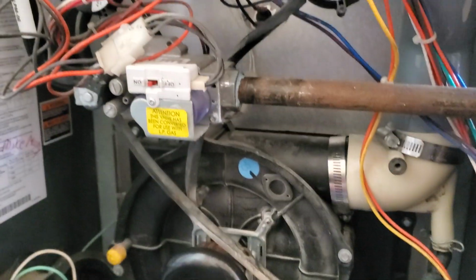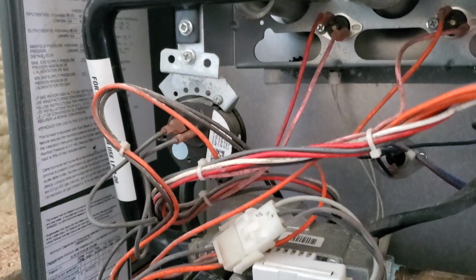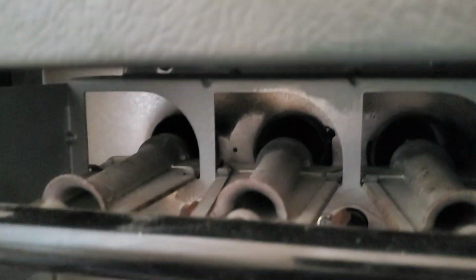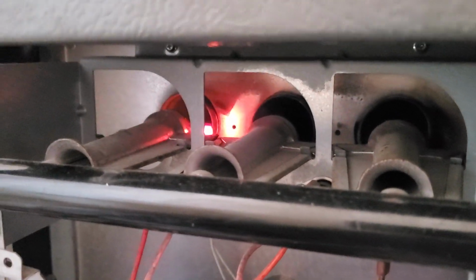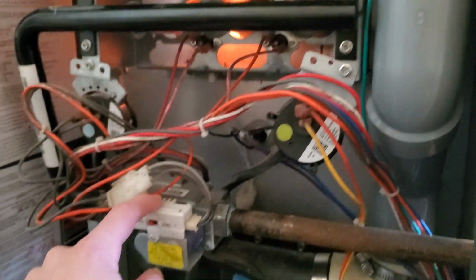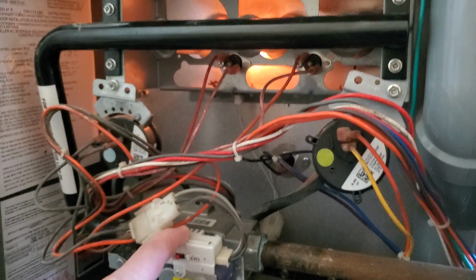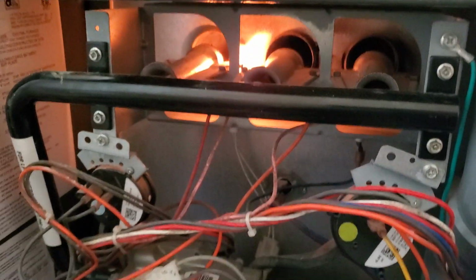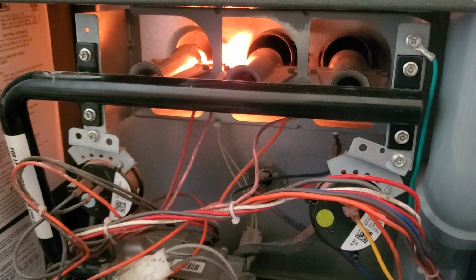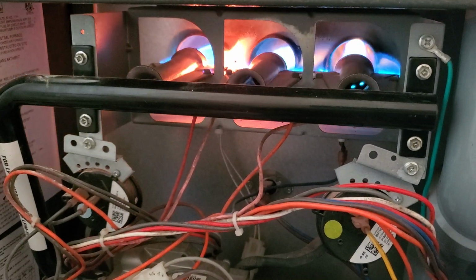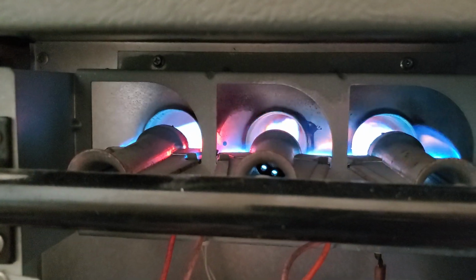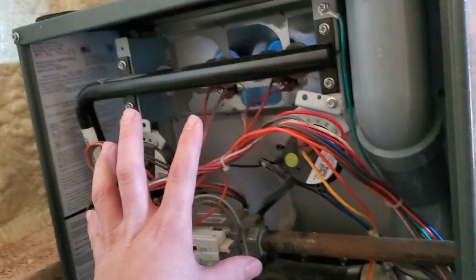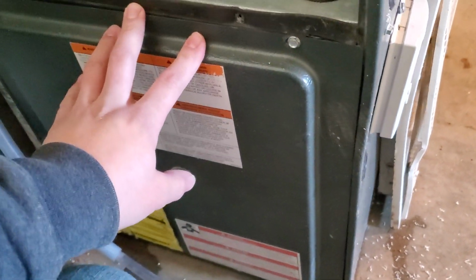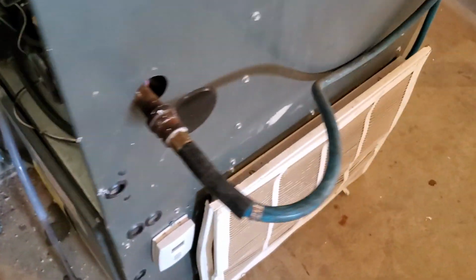Alright, the furnace is coming on. I'll just talk you through how these furnaces work. Combustion blower comes on, and then the igniter comes on after that, once it's confirmed with the pressure switch that the combustion blower is running and that the vent is clear. So we should see the igniter start to glow. There it is. And then a few seconds later we'll hear a click, and that'll be the gas valve energizing, allowing the burners to light. Should happen here in a couple seconds. And then there's usually a little bit of a delay before your main blower, which is down here in the bottom, will come on, probably about 15 seconds or something like that.